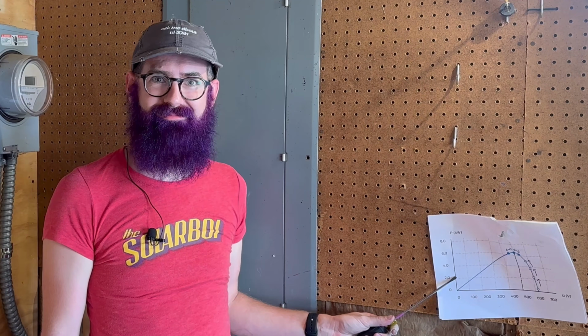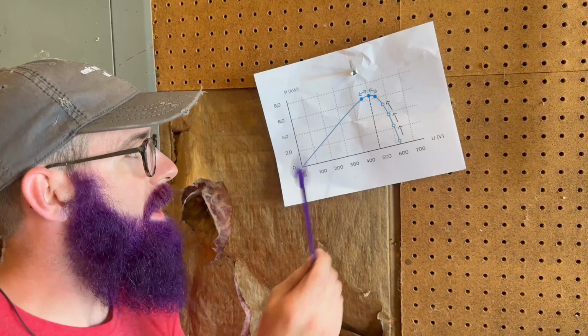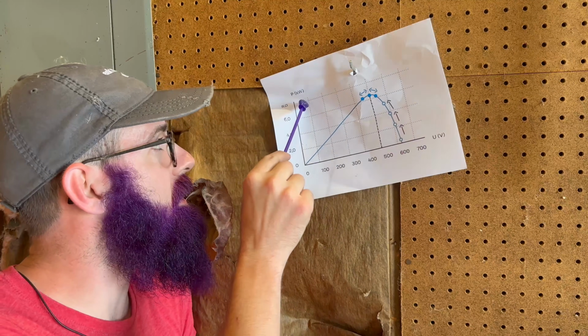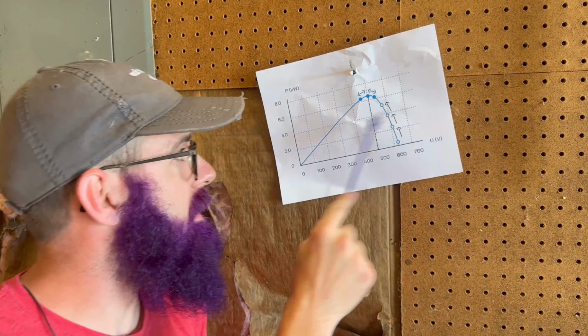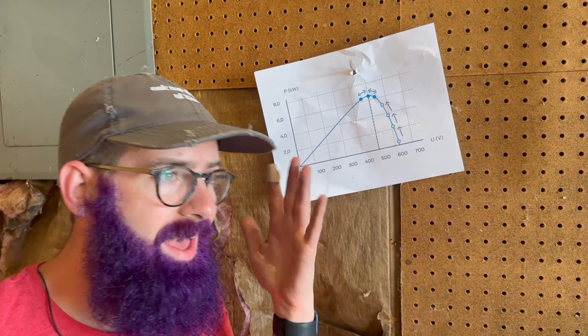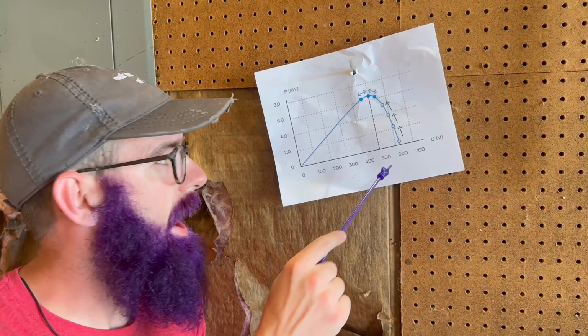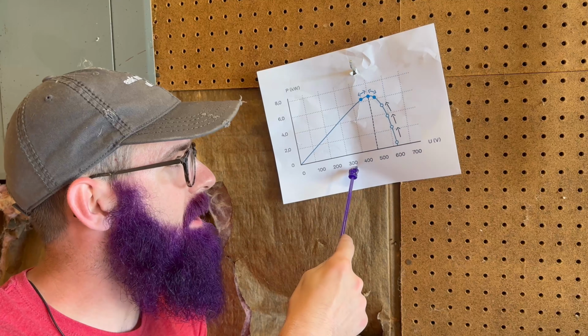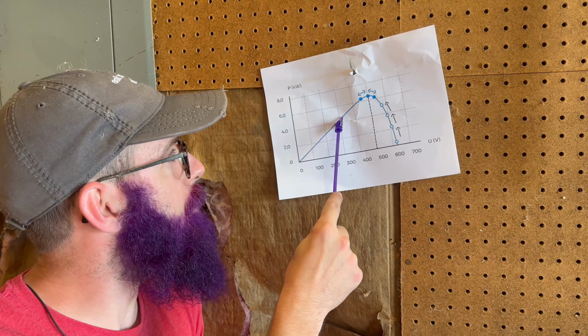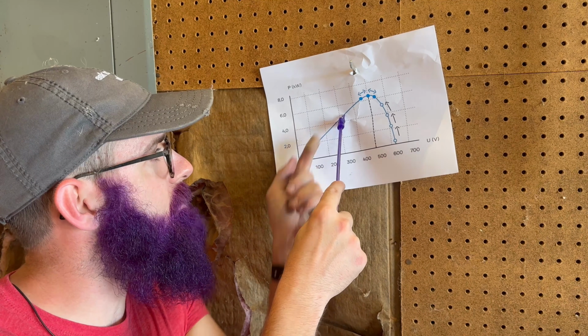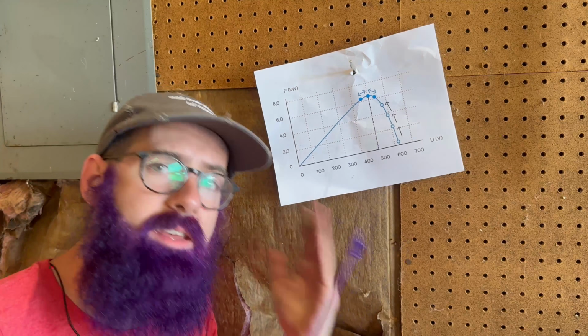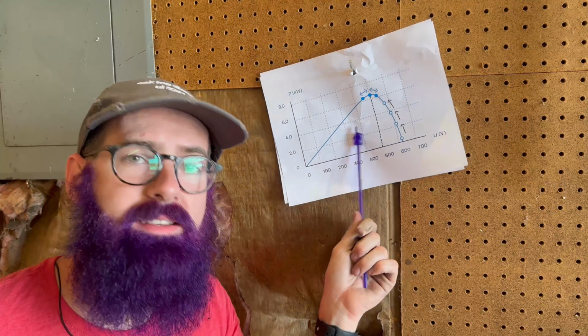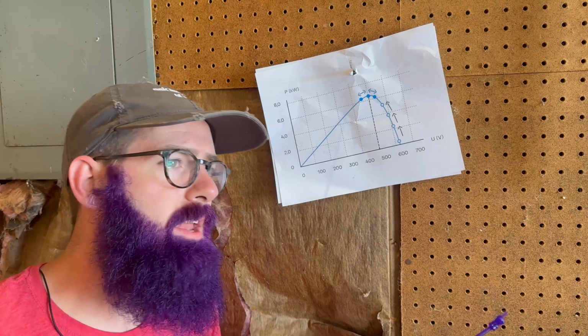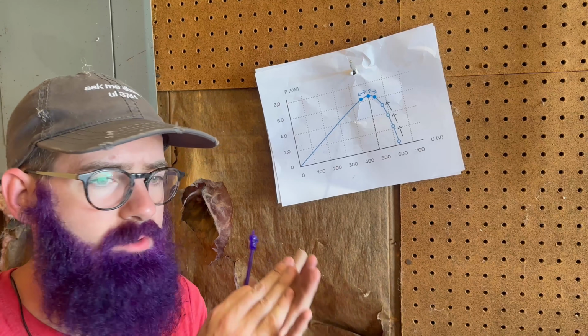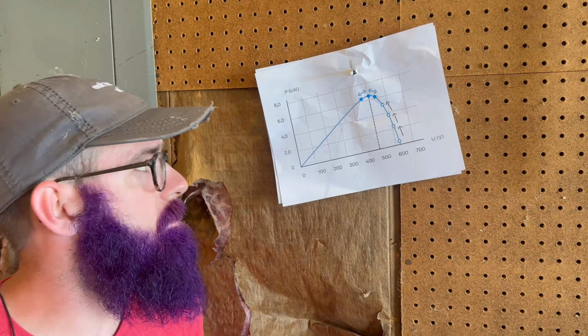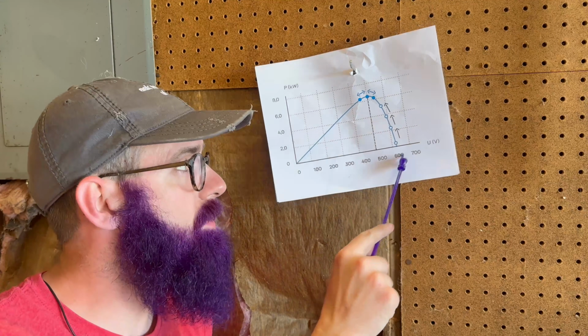the power curve. First off, what is a power curve? Well, this is what that is. You have your kilowatts up here, you have your volts over here. So this graph shows what happens if the inverter runs your solar panels at a particular voltage, say 300 volts, that would be about 4 to 4.5 kilowatts in this power curve example. This is a typical power curve without any shading, just straight up, it's a row of panels, sun's beating down on them. It's gonna be a nice smooth curve like this.